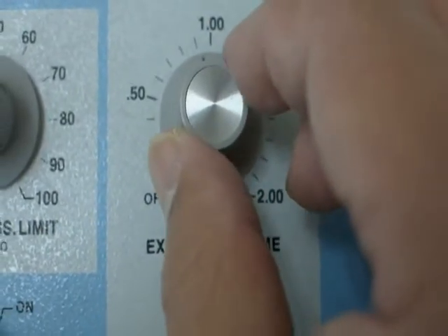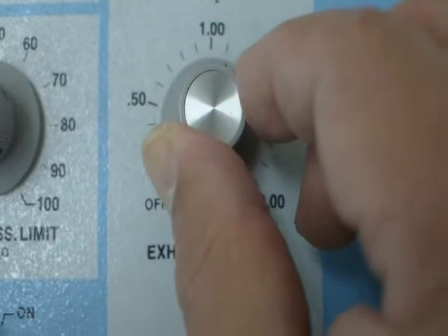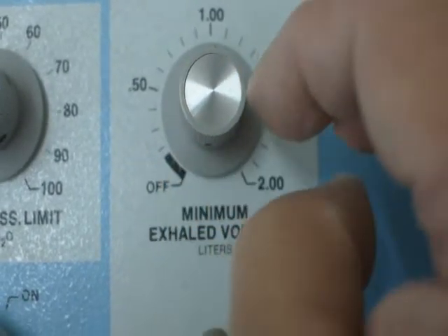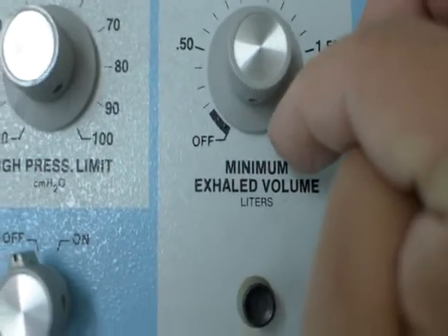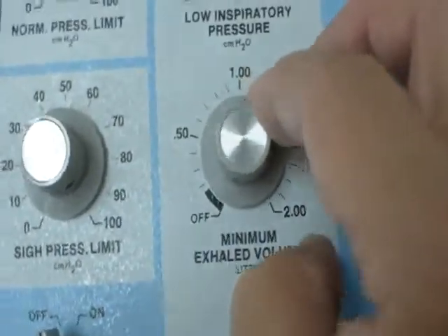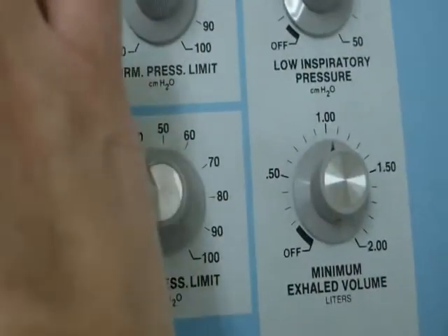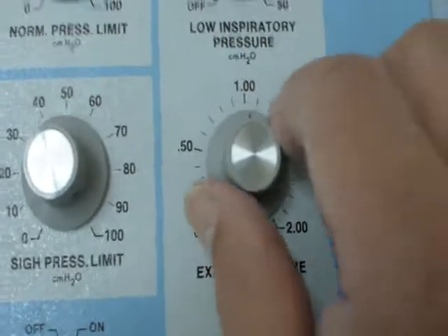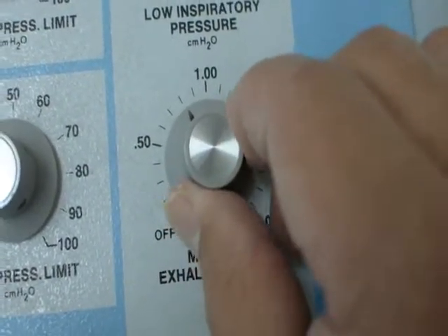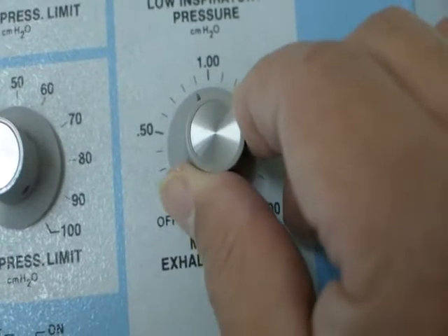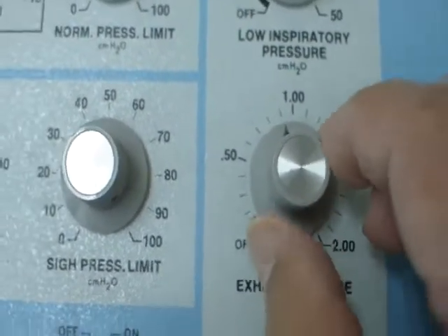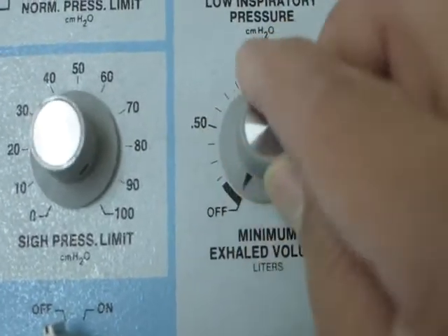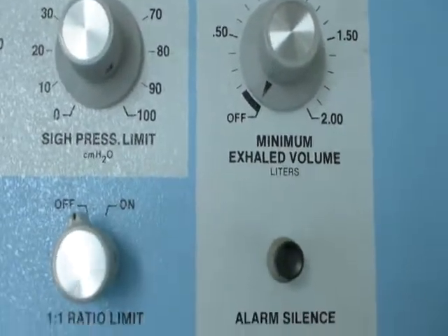And what happens if we set tidal volume at 1 and we set this more than 1? This is going to alarm, because the exhale volume never, okay, has to be equal or a little bit less than the tidal volume. So normally we make sure that it's a little bit less than the tidal volume when we set this, or we can set this to the off position.